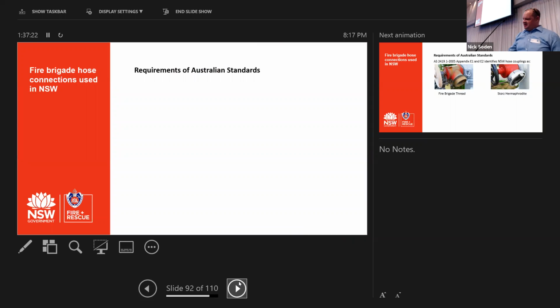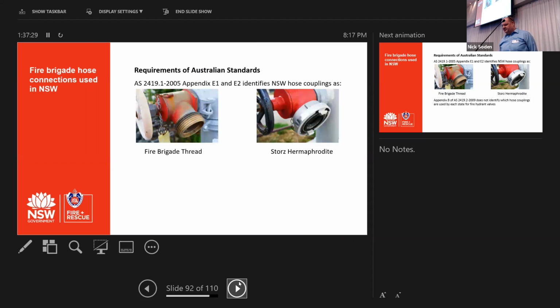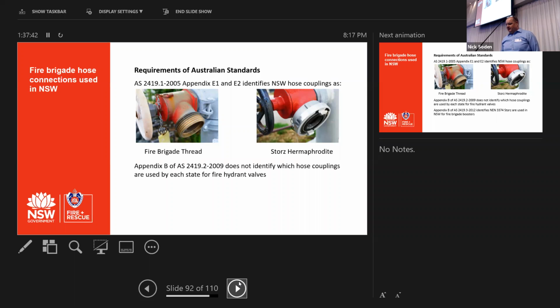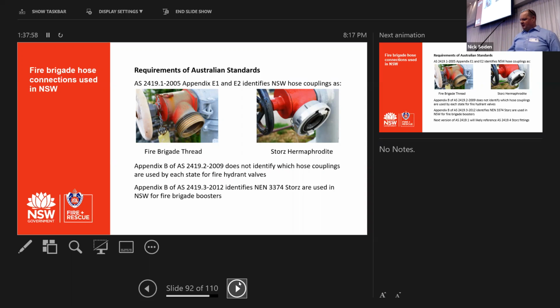Okay, so in New South Wales, fire brigade hose connections. If you look at the current requirement for Australian Standard 2419 Part 1, 2005, in Appendix E1 and E2, it makes reference to both fire brigade thread and Storz hermaphrodite. And that's it, just Storz hermaphrodite. If you look at Appendix B in Part 2, which is fire hydrant valves, it doesn't actually identify which couplings are used in New South Wales. It's a bit of an anomaly, but it's actually missing the second part of the table. And then if you look at Part 3, which is fire brigade boosters, it identifies NEN 3374 Storz are to be used on fire brigade boosters. So you've got 3 different standards, all saying 3 different things.